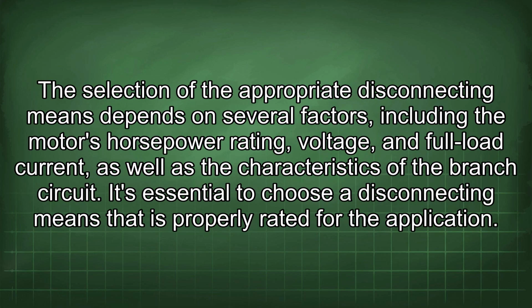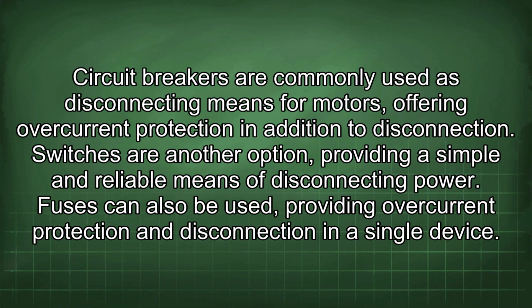The selection of the appropriate disconnecting means depends on several factors, including the motor's horsepower rating, voltage, and full load current, as well as the characteristics of the branch circuit. It's essential to choose a disconnecting means that is properly rated for the application. Circuit breakers are commonly used as disconnecting means for motors, offering overcurrent protection in addition to disconnection. Switches are another option, providing a simple and reliable means of disconnecting power. Fuses can also be used, providing overcurrent protection and disconnection in a single device.